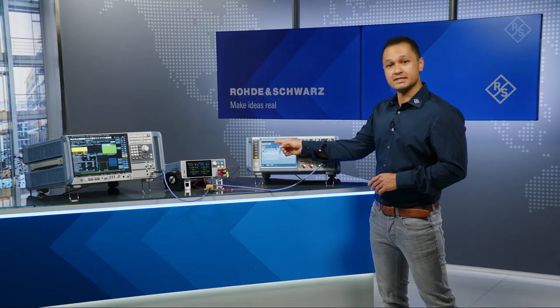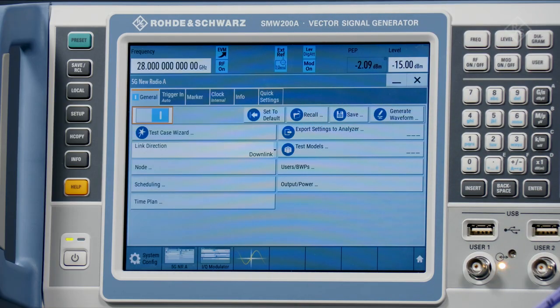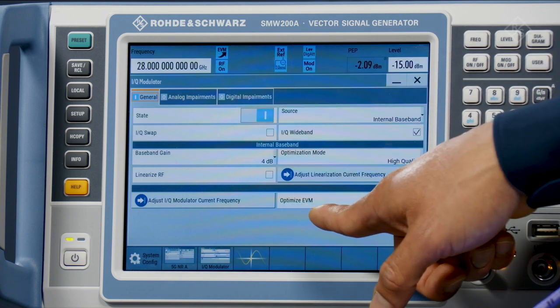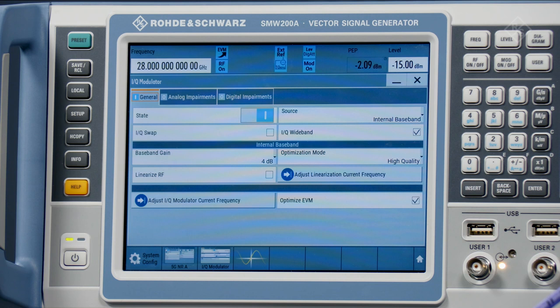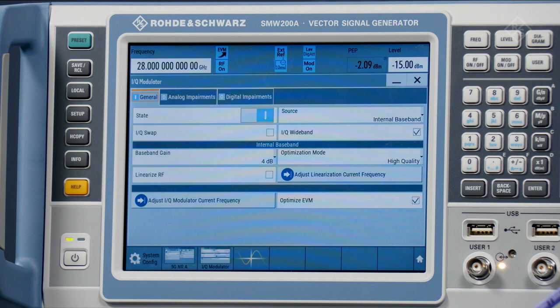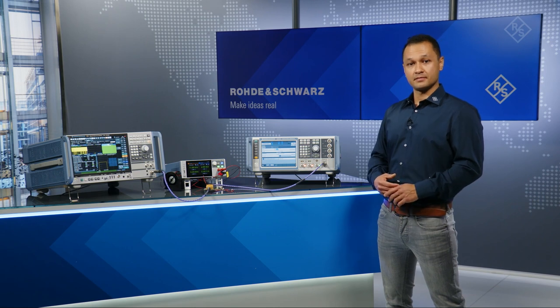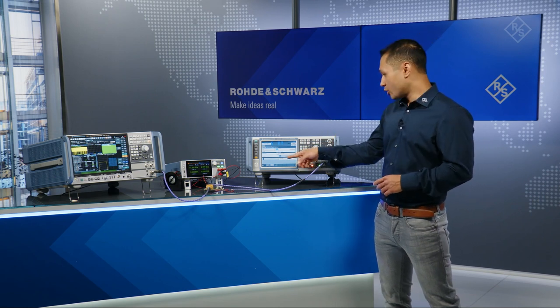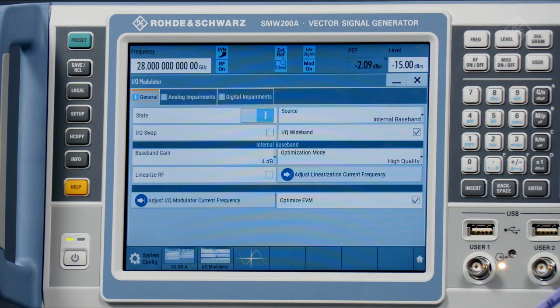After signal configuration, let's turn to the EVM performance of our 5G signal. If required, the pre-existing excellent EVM performance of the SMW can be further optimized by an integrated alignment functionality. When activated, the optimized EVM functionality automatically adapts the settings on the RF path for the selected signal configuration at the desired frequency and level in real-time to ensure optimal EVM performance. By the way, the optimized EVM can also be used for other modulated signals like LTE or WLAN signals. Furthermore, you can utilize optimized EVM when playing your own waveform in our personality.